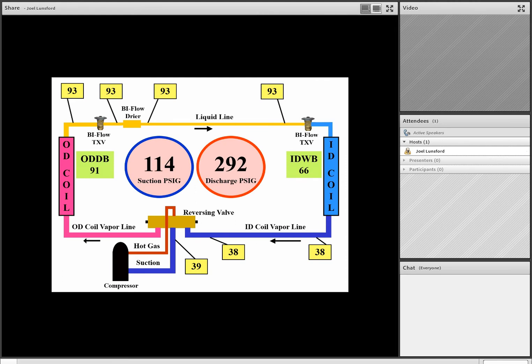We also see that our superheat is low. And if you're working on your subcooling, you'll find your subcooling is a little low. And discharge pressure is low. So look at your superheat, subcooling, pressures, and temperatures, and let's work this out together. So suction pressure is low, liquid pressure is low, superheat is low, subcooling is low. What's your diagnosis?